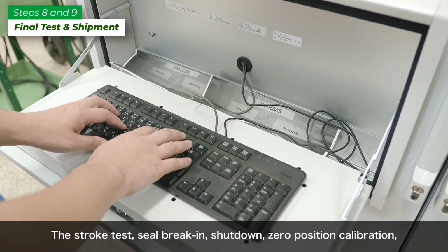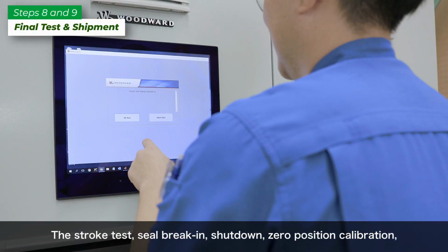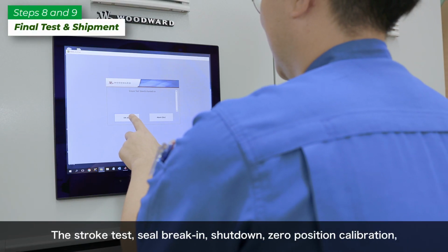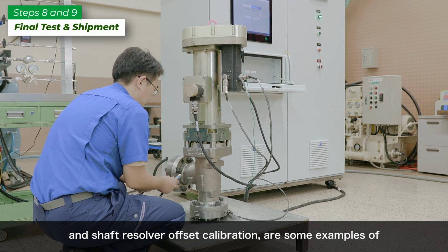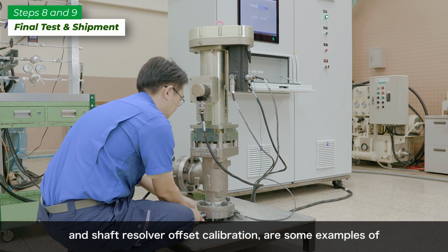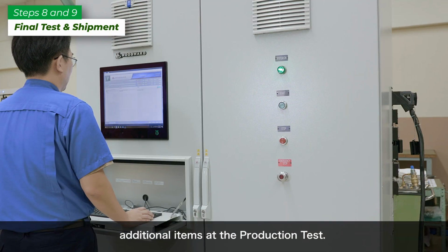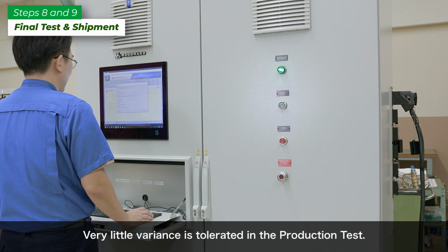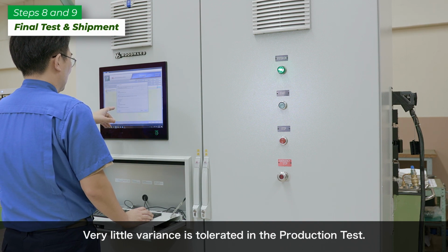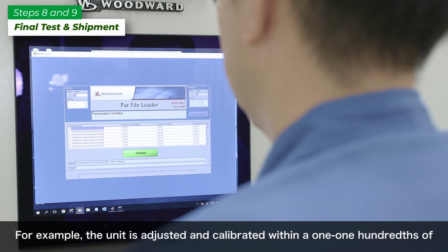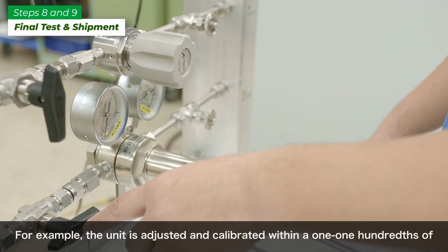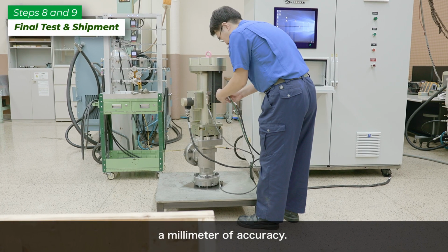The stroke test, seal break-in, shutdown, zero position calibration, and shaft resolver offset calibration are some examples of additional items in the production test. Very little variance is tolerated in the production test. For example, the unit is adjusted and calibrated within 1/100th of a millimeter of accuracy.